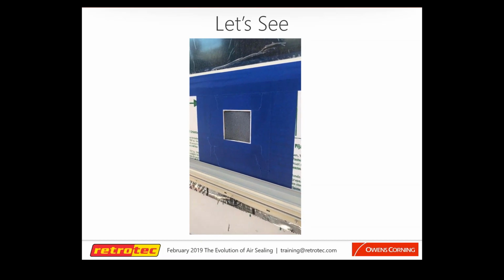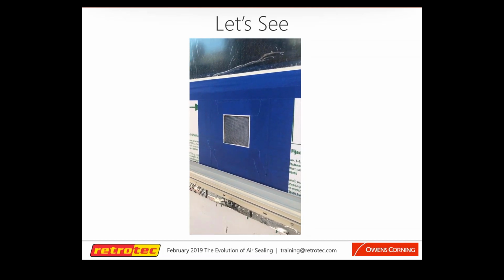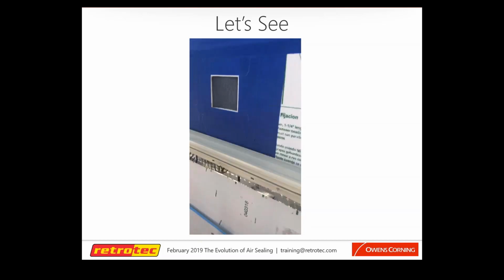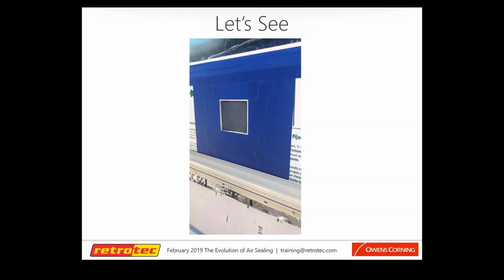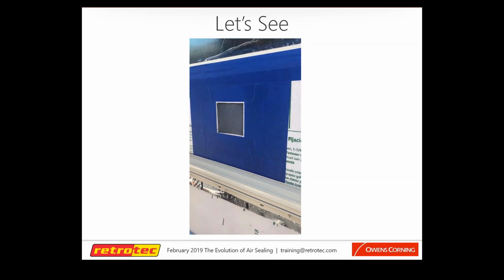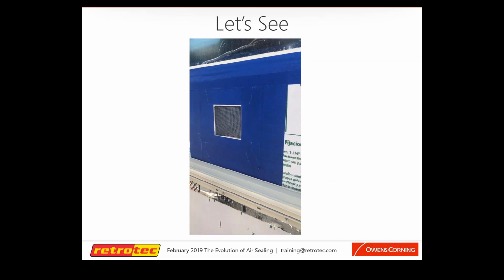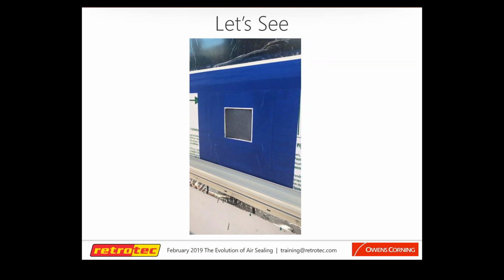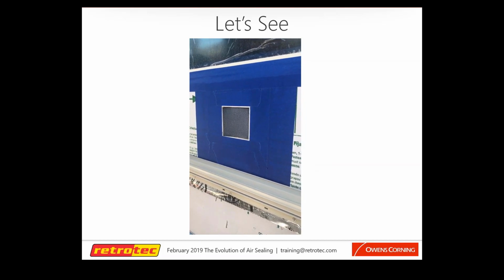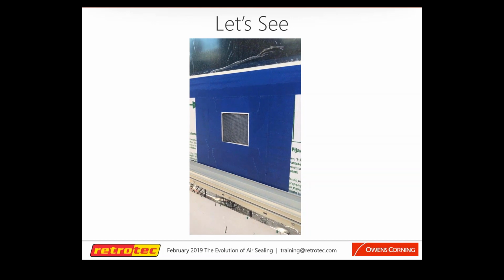And then we'll also print out that report to make sure that they get the test results to know where it's going to be. Now, I know the HERS raters out there are thinking the same thing I was when I saw this. So this is a pressurization test. We do depressurization. And the reason why we're doing pressurization here is to find the holes. We do depressurization so all the dampers are closed at the normal state and the house is under normal living conditions. That's one of the main reasons why we do a depressurization on a blower door test.